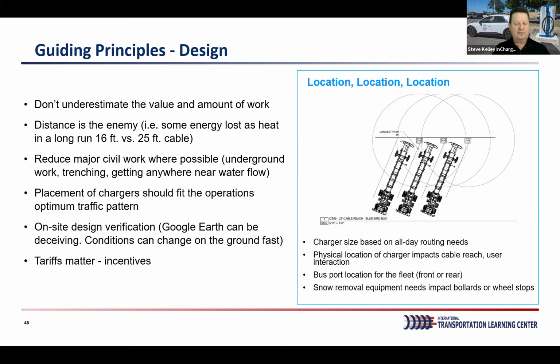The other real challenge is civil and construction. When we go on site, we want to make sure we're not hitting underground utilities, and that it's easy to navigate. Being closer to the electrical panel is critical for lowering cost and placement so things fit. Sometimes we have to restripe and redesign the yard depending on what they currently have and where to put the chargers. This is critical to get right, a good solid design for where to put the charger, how to lower installation cost, and making sure the cords fit the style you have for the bus, whether you're pulling it in or backing in.